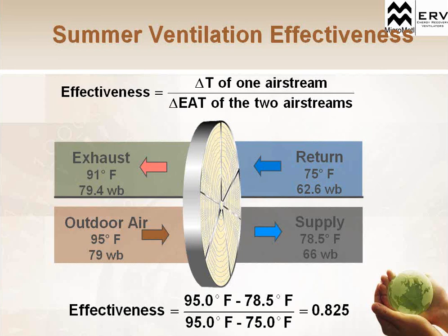I mentioned with the code, there is a 50% effectiveness of an energy recovery device that's required. Now, how they calculate that effectiveness of the wheel itself, of that material, is basically how efficient the material in that wheel is of taking the energy and transferring it from one airstream to the other airstream. To calculate that percent of effectiveness, we take the change in temperature of one airstream all the way across and the change of the two entering airstreams on either side of the system, so the return air coming in and the outdoor air coming in. How much did we improve that temperature?